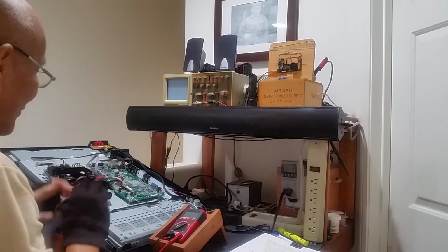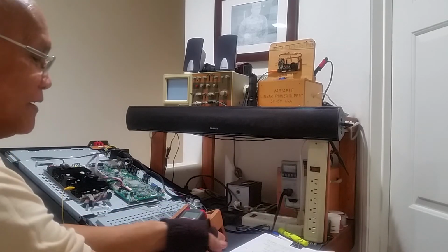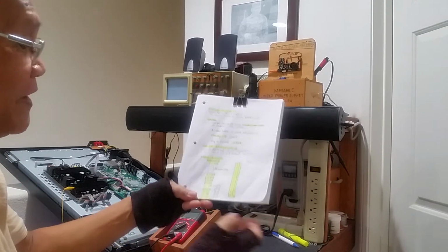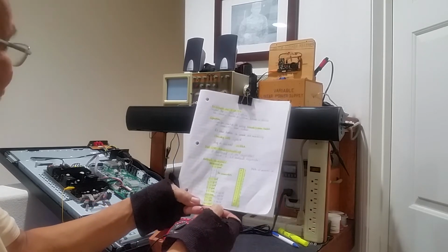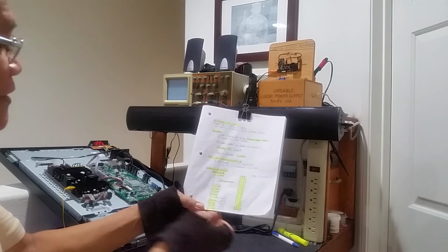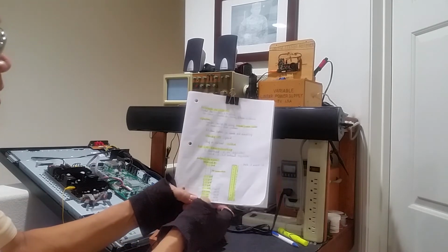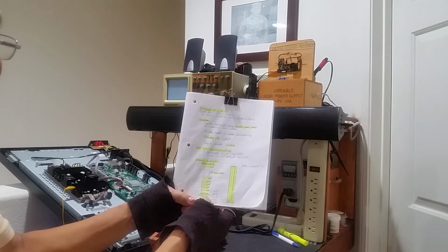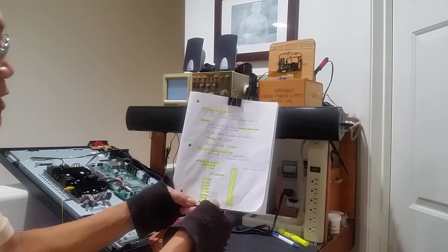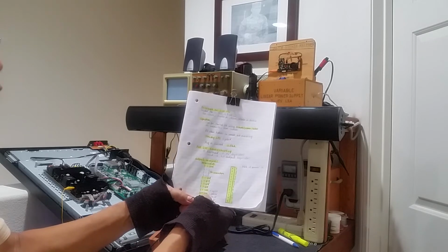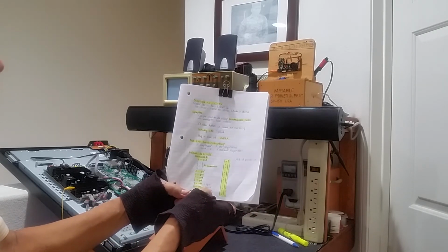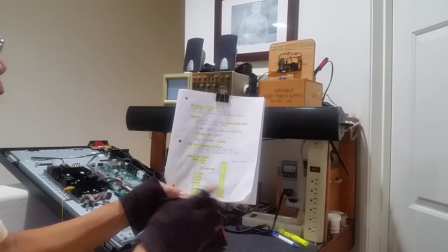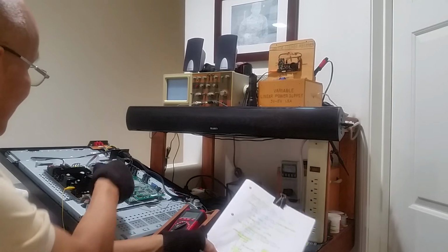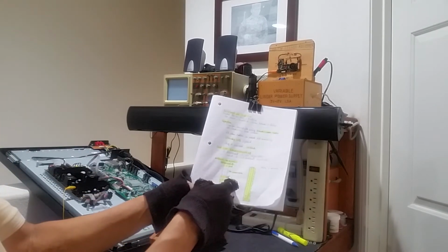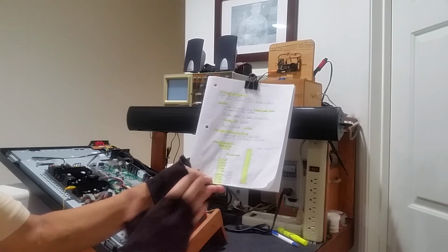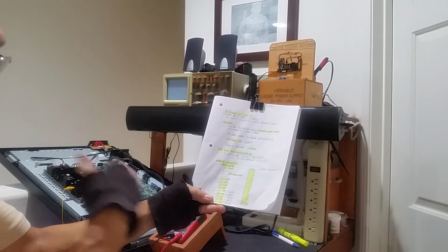So for output terminal number 1, live testing shows: terminal 13 is 24.03, and the schematic marking says it should be 24 volts — that's fine. The next one is 24.11, also marked as 24 volts — fine. And so on: 24.11, 24 volts, 24.11. So for the last five terminals on the first output terminal, all the voltages are fine — it seems our power supply is correct.